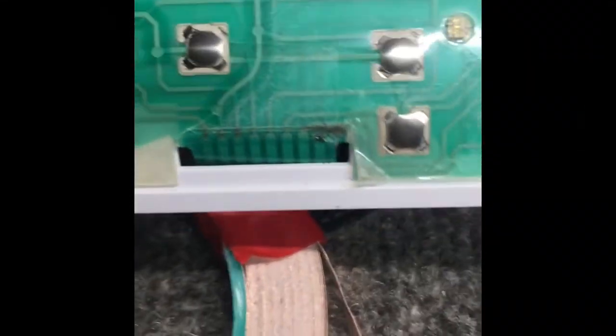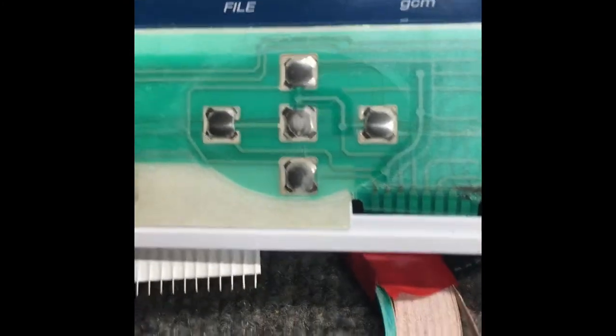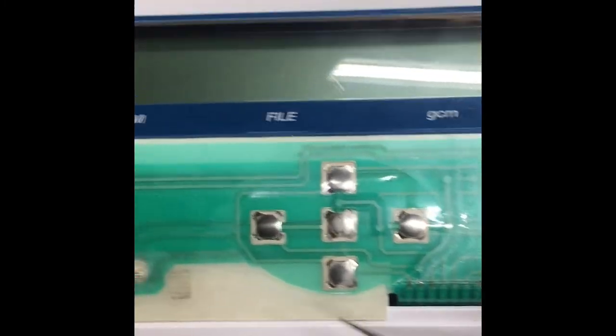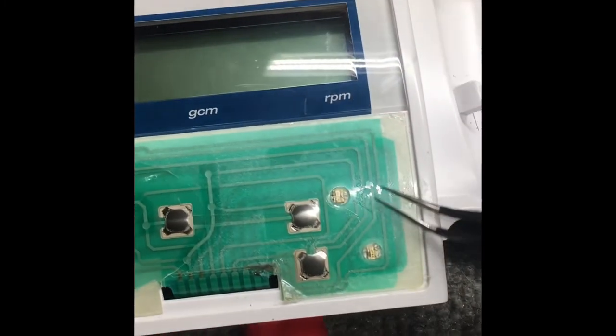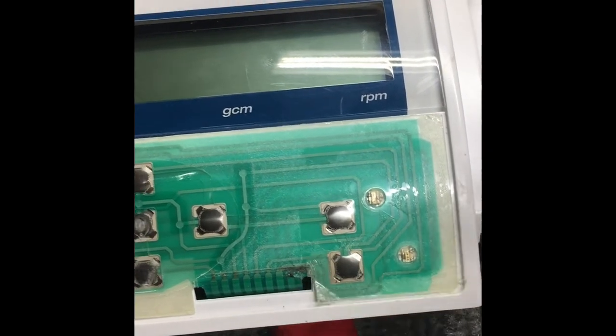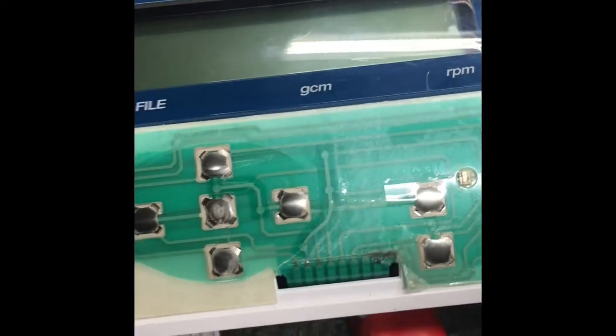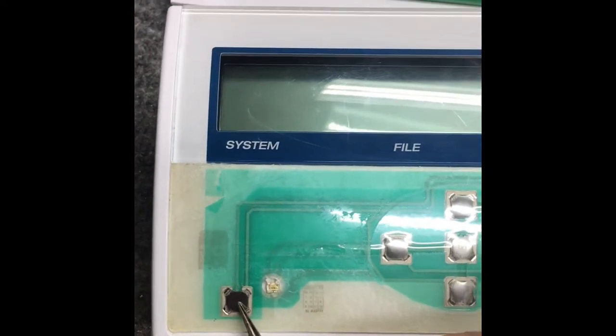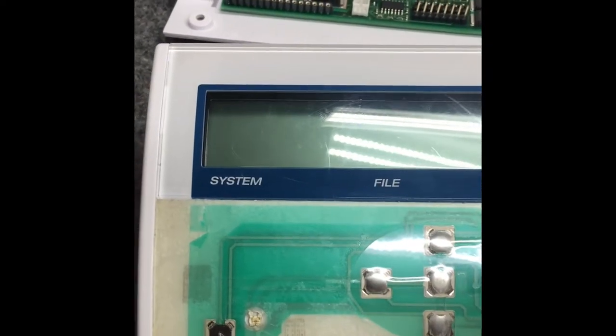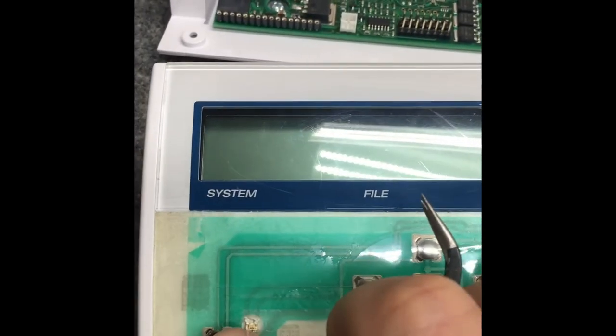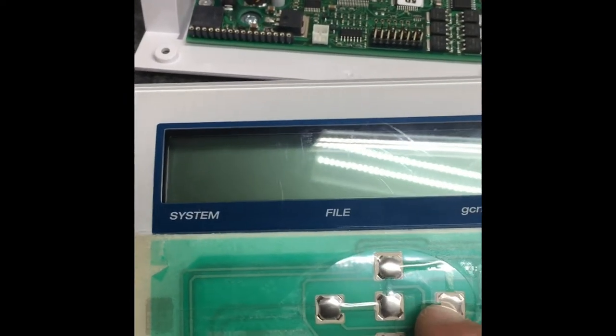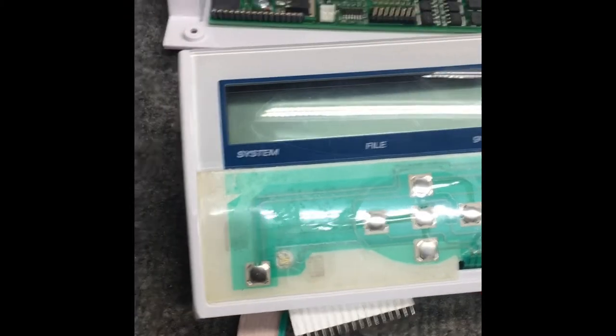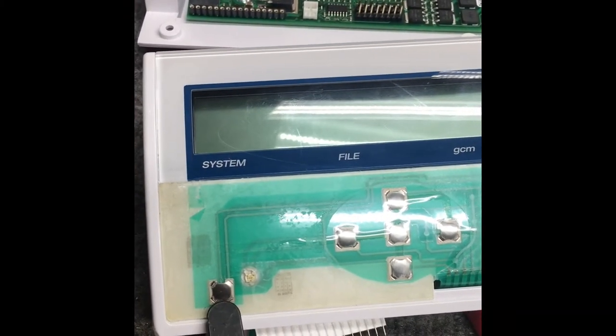Because the damage on this membrane here, the power switch, we visually traced out where the power switch is connecting to. This is the power switch. The two lines come down, they go around the LED, come over here and they connect to these first two contacts here, first two pins. Because of the damage, what we're going to do is we're actually going to remove this little switch assembly itself and replace that with an actual micro tactile switch. It might be a slightly different height than these, but really shouldn't matter at all. I'm sure the customer just wants this thing back in his inventory. This was a spare for his dental practice.